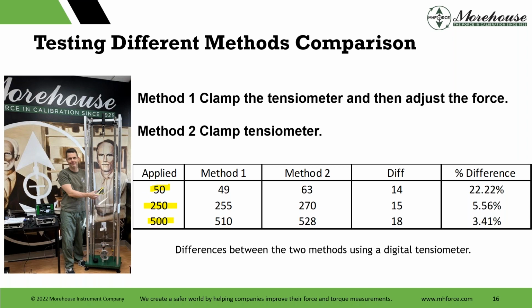Anyway, so we applied lots of different forces, 50, 250, and 500. And I used method one, clamp the tensiometer and adjust the force. Guess what? They read 49 at 50, 255 at 250, and at 500, 510. If you notice the differences, they're very close to nominal. So maybe this instrument was adjusted or spanned using the dead weight method. I'm not completely sure, though I know who calibrated the tensiometers, and that's the method they use, so we can conclude that's how they were spanned, though they might have been done at the factory as well and just sent to us.